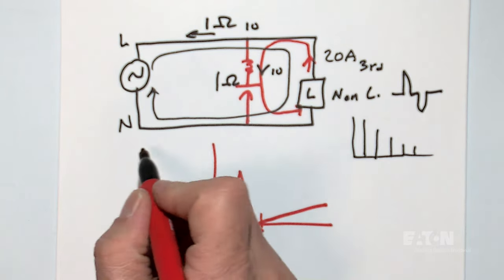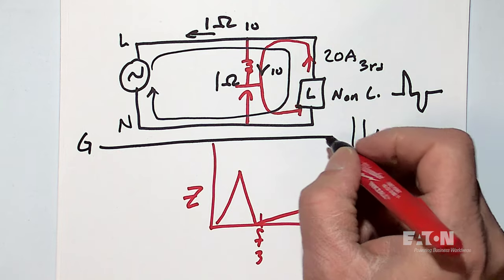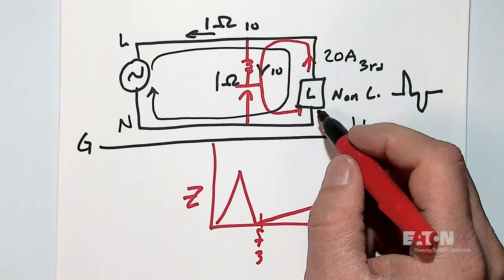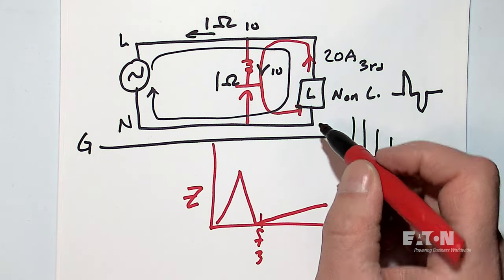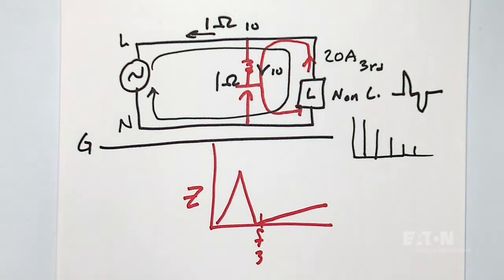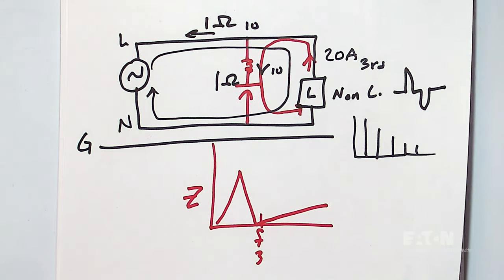Notice that this is your line and this is your neutral. My ground is simply here for safety and protection of people. That current does not flow through ground, just like it doesn't flow through ground when you have a normal power system current that flows to the load. Because the only time I want current in my ground is when I have a fault.